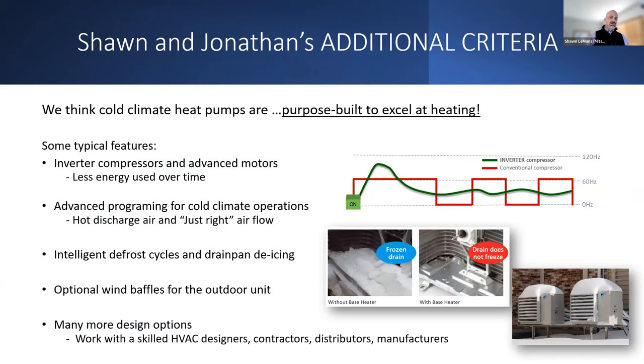It's going to be looking at possibly the inverter compressors and the motors that go into this and the efficiency of use over time, rather than this on and off cycle that you see with typical 1 and 2 speed systems. Looking at the programming, the algorithms, how does this system handle these patterns? And one key item is looking at a hot discharge air temperature and just right airflow for matching up the need with the capability.